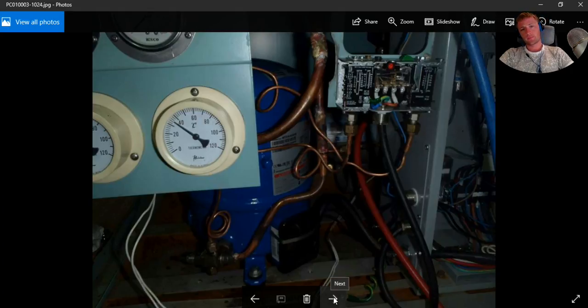And the compressor was started. The problem was in the valves, really. How did we find that? What is happening is, when your compressor starts, the pressure slightly increases, and after that your compressor cannot increase more pressure. It's working without any load, and the pressure goes back. So the protection will then trip your compressor. That's how it works, and that will happen.